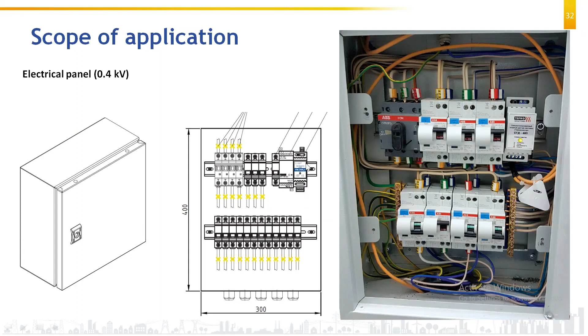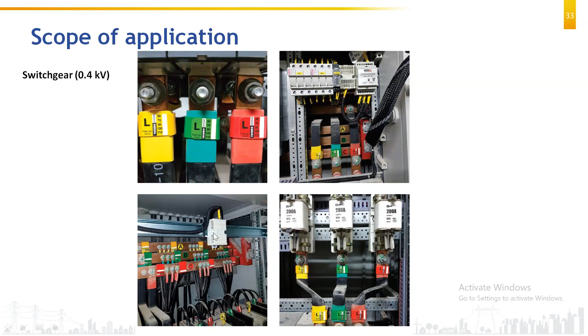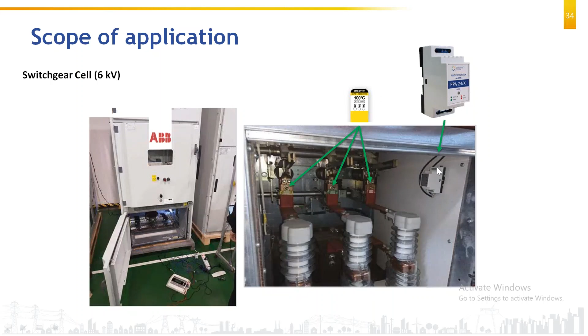Then again, a little bit higher, MCC panels, where the stickers will be installed in this fashion. And here we have used the multi-channel FPA. These two are sensors, and then we have an FPA here. And then in a 6.6 kV switchgear panel, we will install at the contact terminations, and the FPA will be installed in the same cabinet. I hope it is visible.